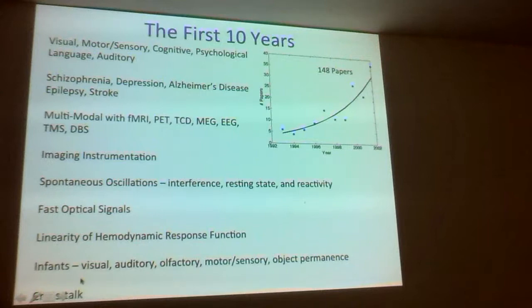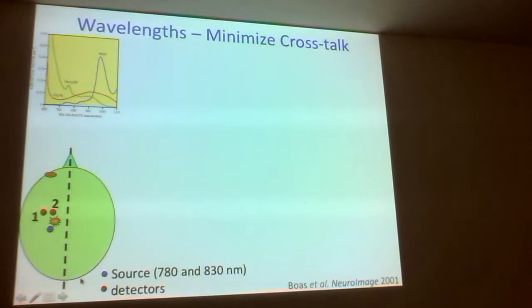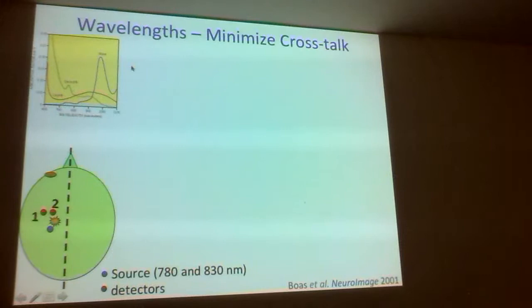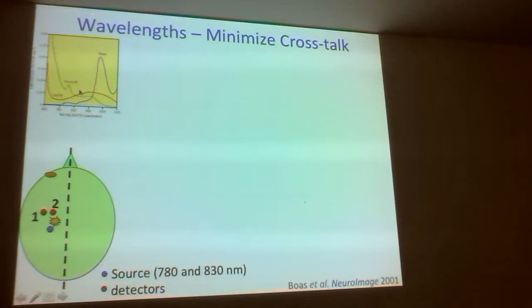One big change in the first 10 years was actually the choice of wavelengths. In the first 10 years, everyone was using 780 nanometers with 830 nanometers — the idea being the isosbestic point at 800 nanometers, with one wavelength shorter for deoxyhemoglobin sensitivity and one longer for oxyhemoglobin. But when converting from optical density changes to concentration changes, you had to make assumptions about the differential path length factor, and any small errors would be amplified because the spectral differences were not that large.